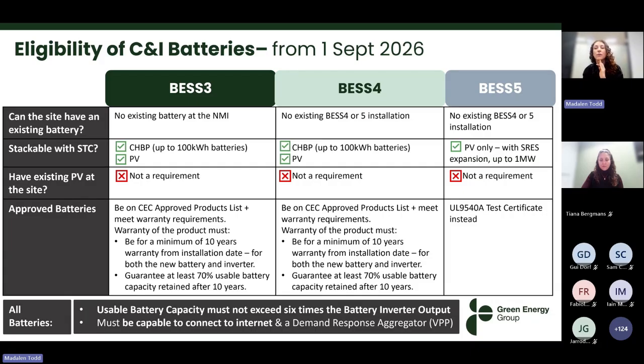So under BESS 3 and 4, the batteries must be on the CEC approved batteries list, and they have to be valid and active at the time of install. They also must meet the warranty requirements of the regulator, IPART, to be eligible for the scheme. That means they must have a warranty on the product for at least 10 years and guarantee that at least 70% of the usable battery capacity is retained after 10 years from the installation date. So not the manufacturer date, not the date that it was shipped from the manufacturing country, just the installation date.